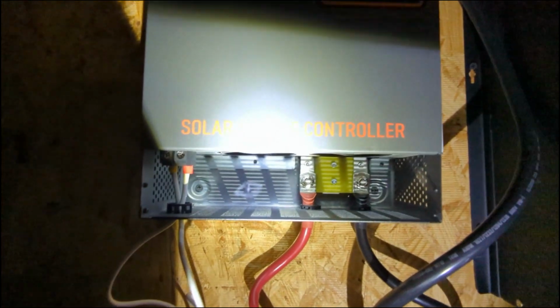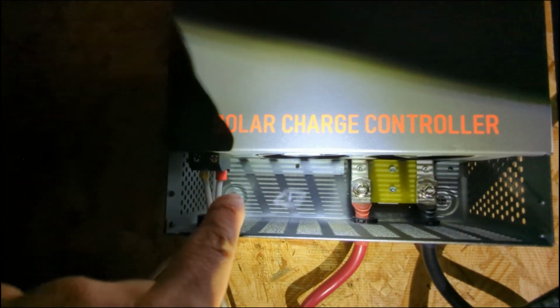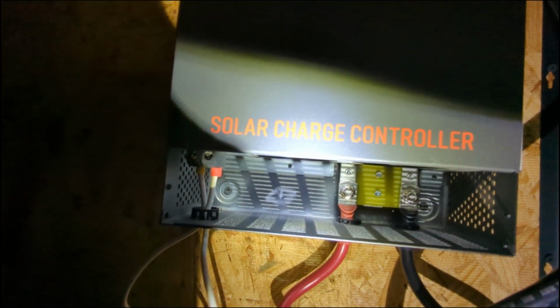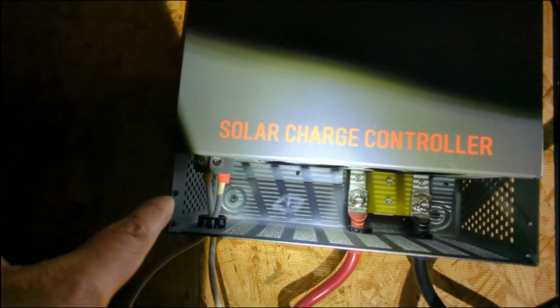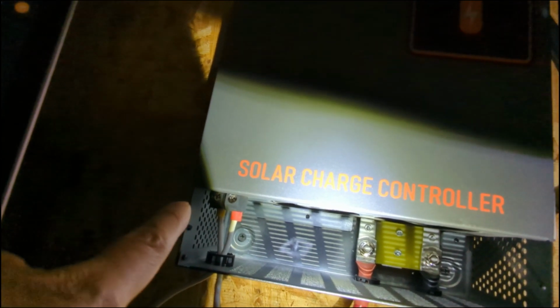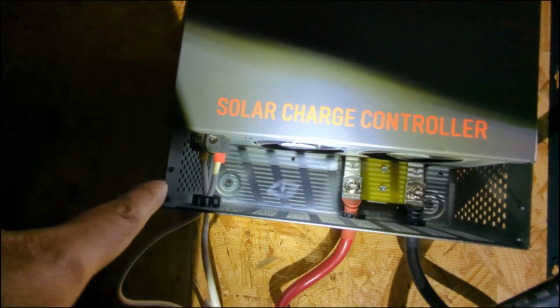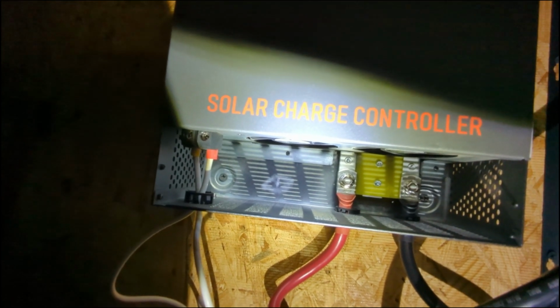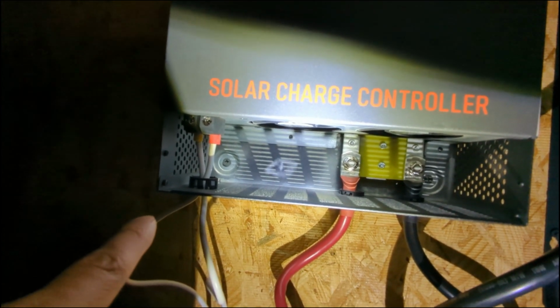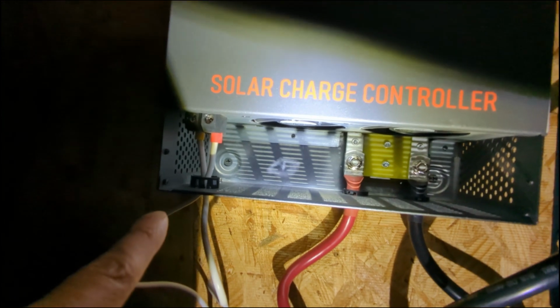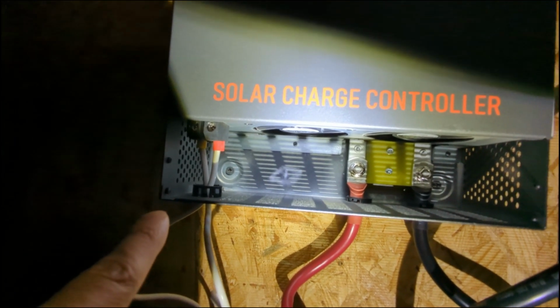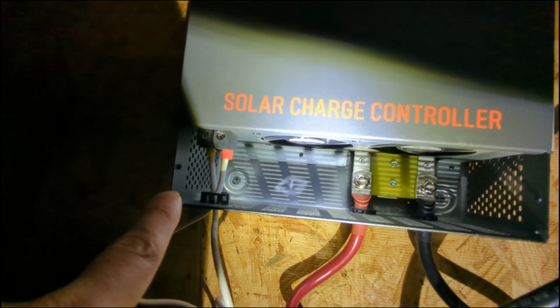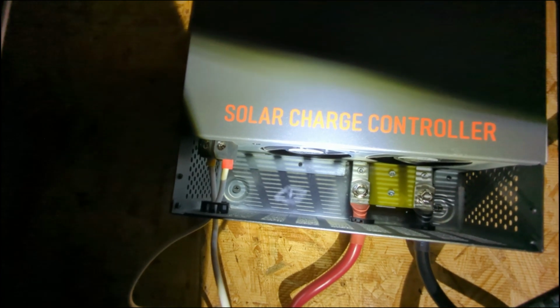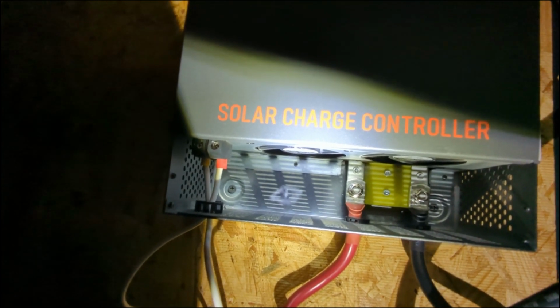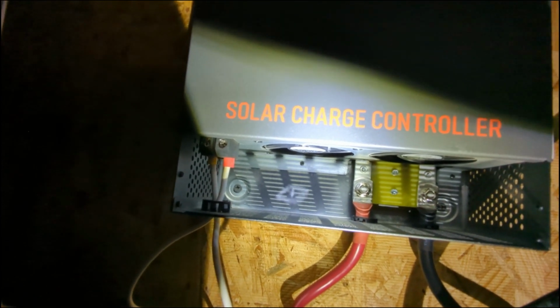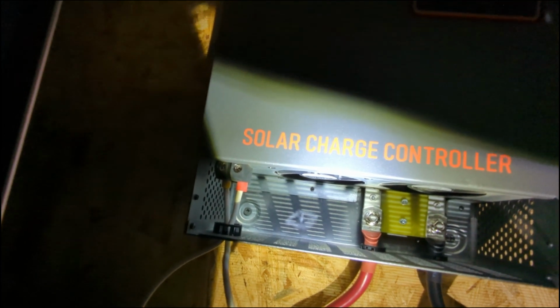Let's take a look at the connections. On the left-hand side, we have our PV terminals. It's your typical screw type terminals. I'm running 8-gauge wire in it. I feel like it probably has a little bit more room to support up to 6-gauge wire, but because this is such a high voltage unit, the amperage shouldn't be as high as one of those lower voltage MPPT controllers.